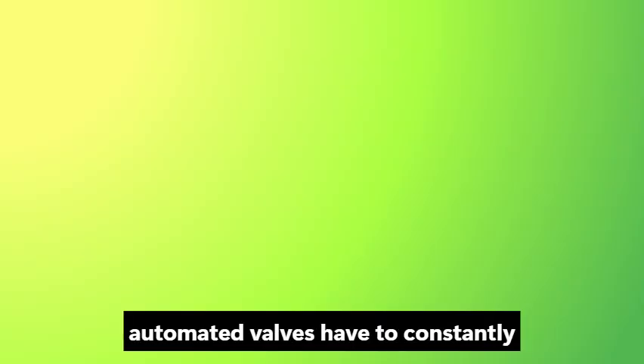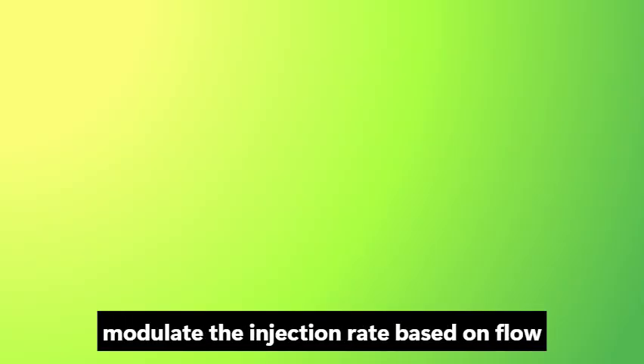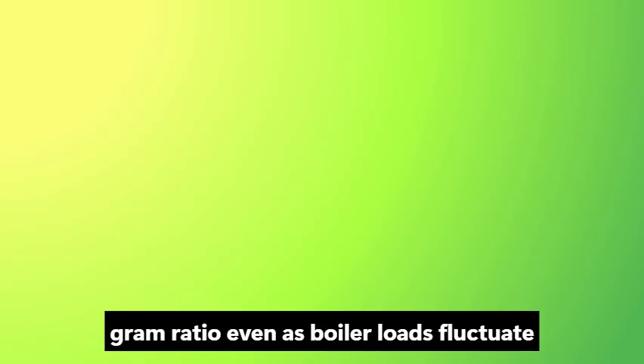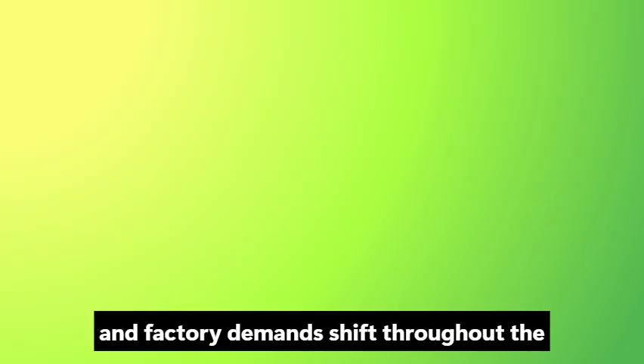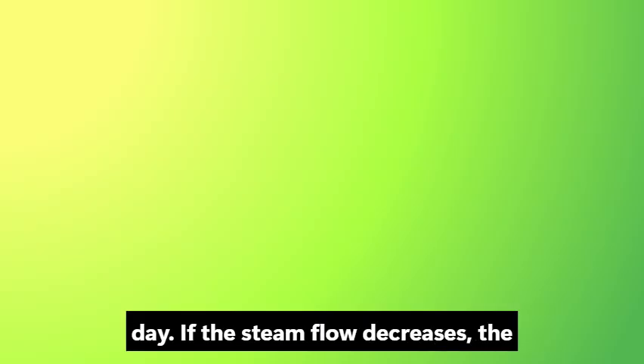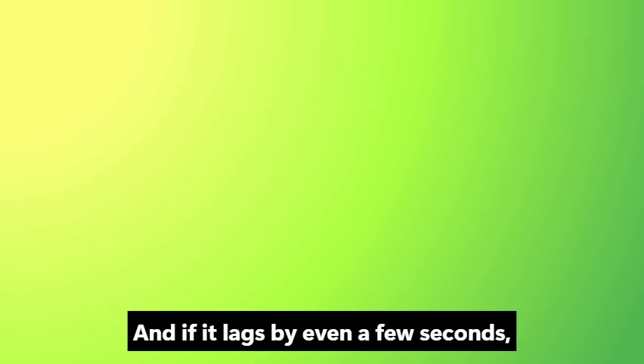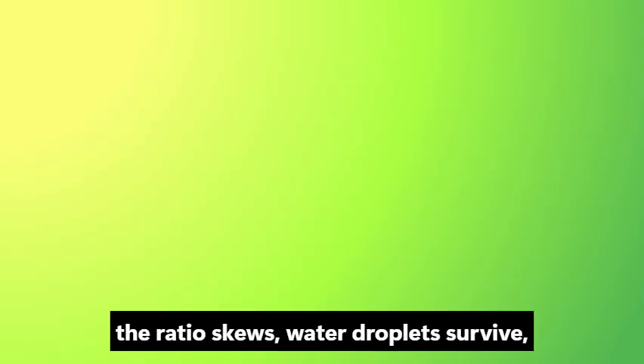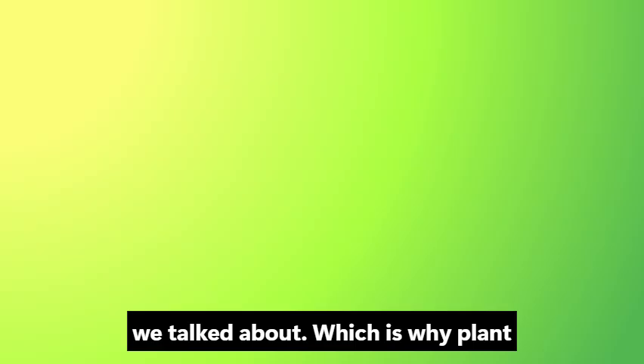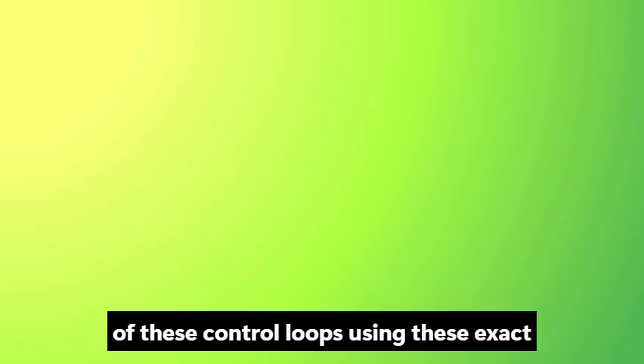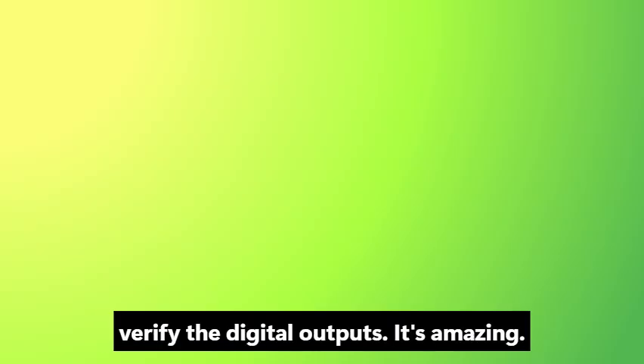Because those automated valves have to constantly modulate the injection rate based on flow meters, right, to maintain that exact 37-gram ratio. Even as boiler loads fluctuate and factory demands shift throughout the day, if the steam flow decreases, the water valve must instantly throttle back. And if it lags by even a few seconds, the ratio skews, water droplets survive, and you get that downstream water hammer we talked about. Which is why plant engineers constantly monitor the tuning of these control loops, using these exact manual mass balance calculations to verify the digital outputs.